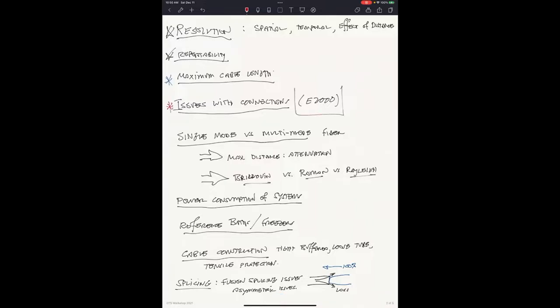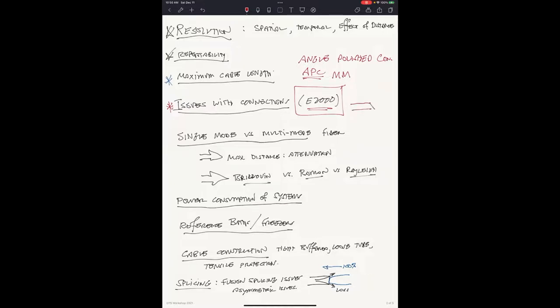On connectors: we use an industry-standard E2000 connector, and you need an angle-polished connector — an APC. When you ask for an APC E2000 with multimode fiber, vendors will be surprised, as this is not standard — it's a custom job. The end of the fiber is polished at an angle so that any stray photon hitting the angle will be bounced out of the fiber rather than directly backscattered. This is very important. The angle is oriented within the E2000 so that when the next fiber connects, it matches up to that angle and photons cross the connection.